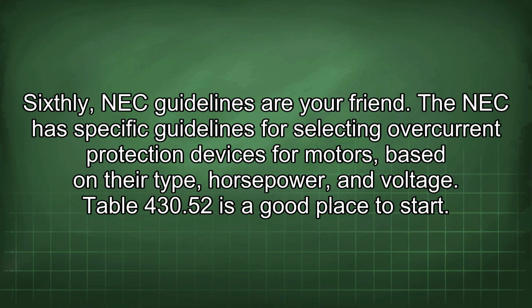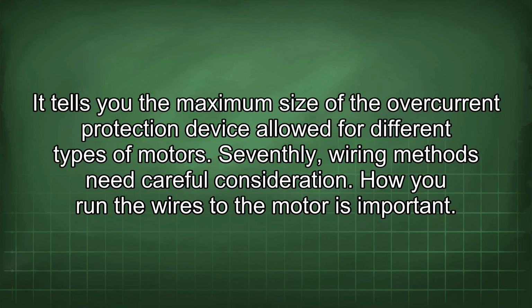Sixthly, NEC guidelines are your friend. The NEC has specific guidelines for selecting overcurrent protection devices for motors based on their type, horsepower, and voltage. Table 430.52 is a good place to start. It tells you the maximum size of the overcurrent protection device allowed for different types of motors.